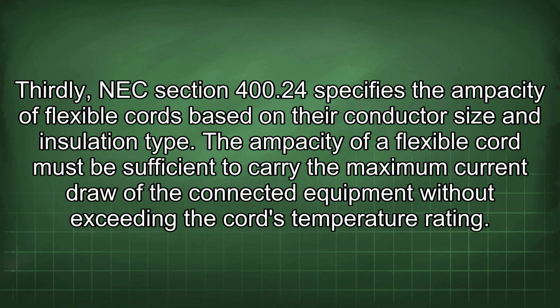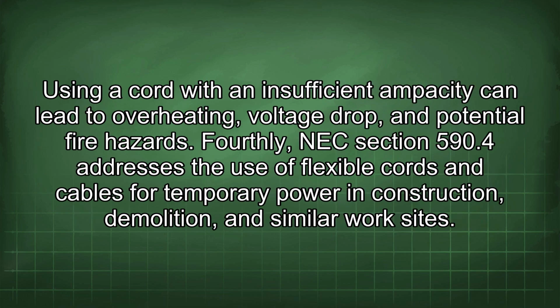Thirdly, NEC Section 400.24 specifies the ampacity of flexible cords based on their conductor size and insulation type. The ampacity of a flexible cord must be sufficient to carry the maximum current draw of the connected equipment without exceeding the cord's temperature rating. Using a cord with an insufficient ampacity can lead to overheating, voltage drop, and potential fire hazards.